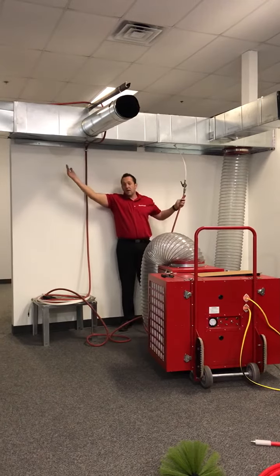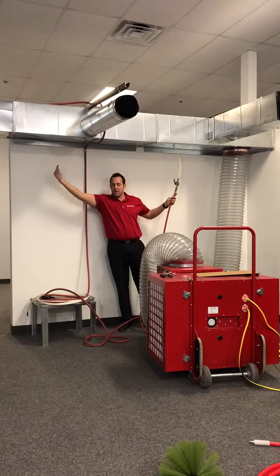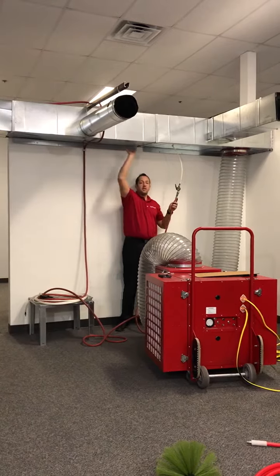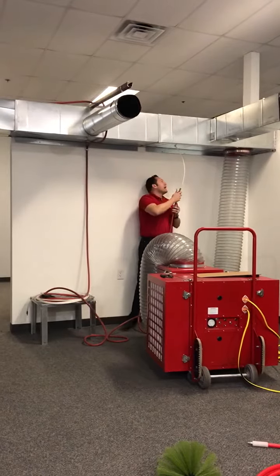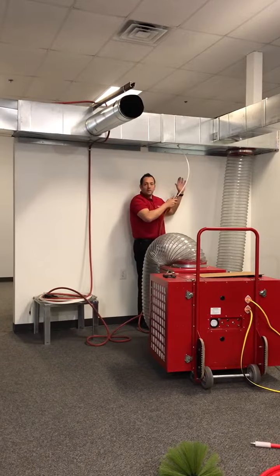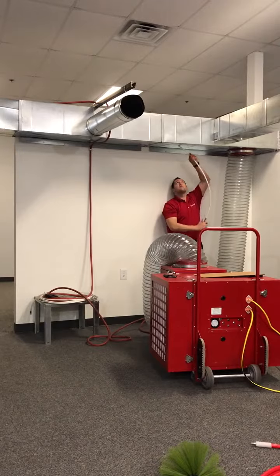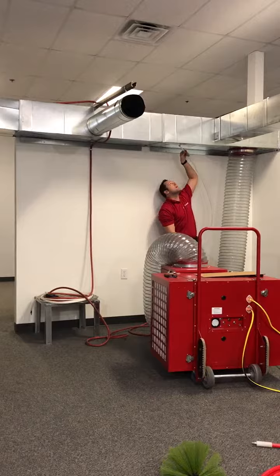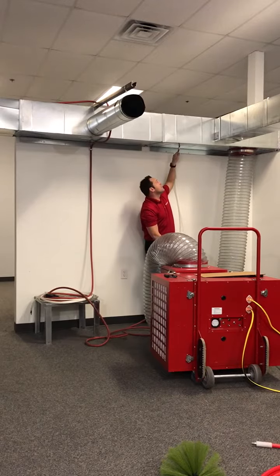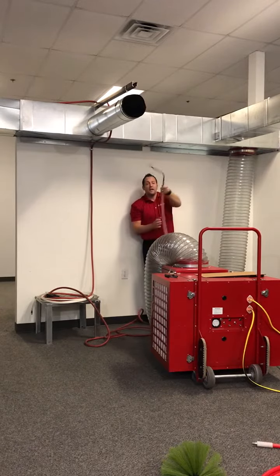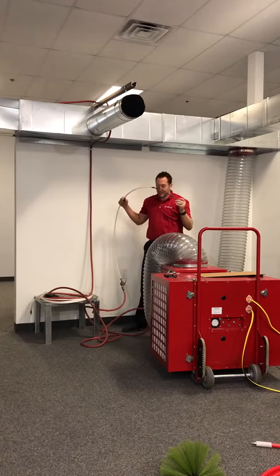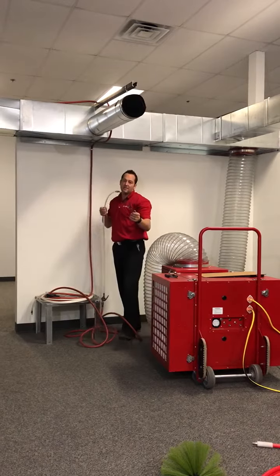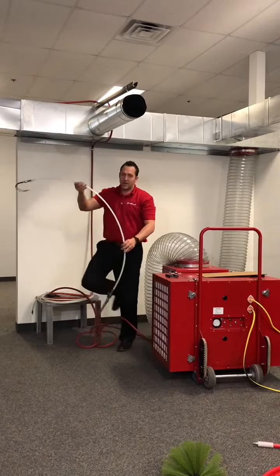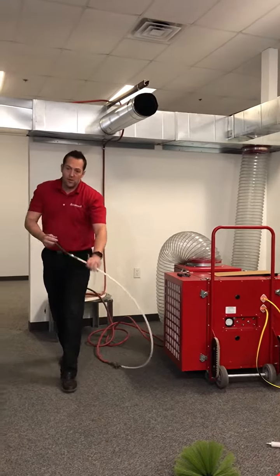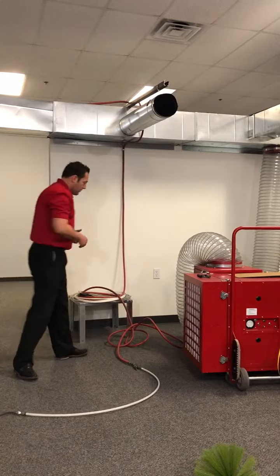Again, if I'm coming from the opposite end, then I'd use a forward air sweep. So now that dust and debris is being pushed in conjunction with it as well. Just be cognizant of which way you're going as you're going. At that point, you pull it out. Again, the whip size will be dictated by the actual size of the ductwork itself. So we'll put this down as we go through.